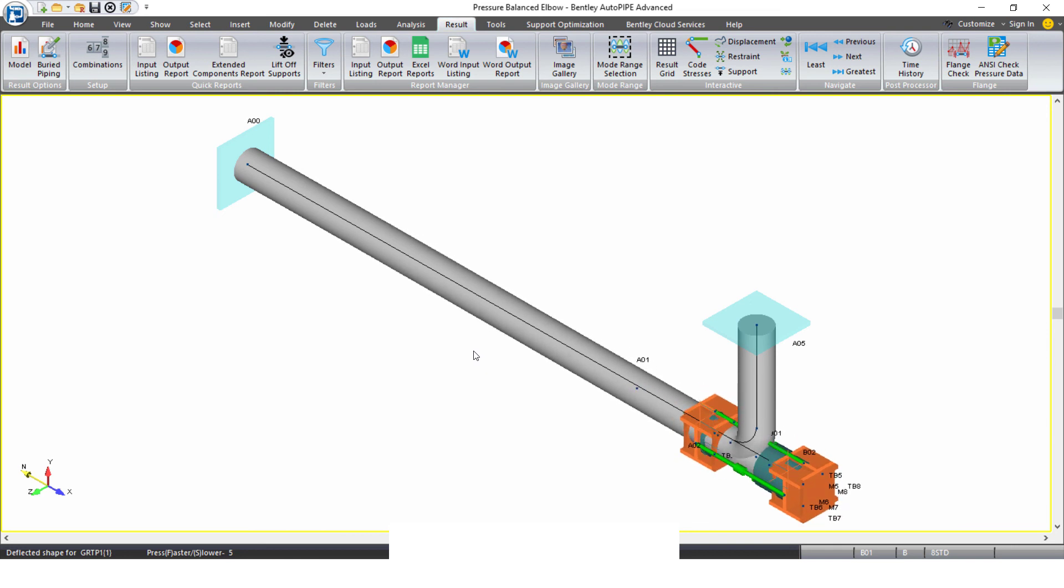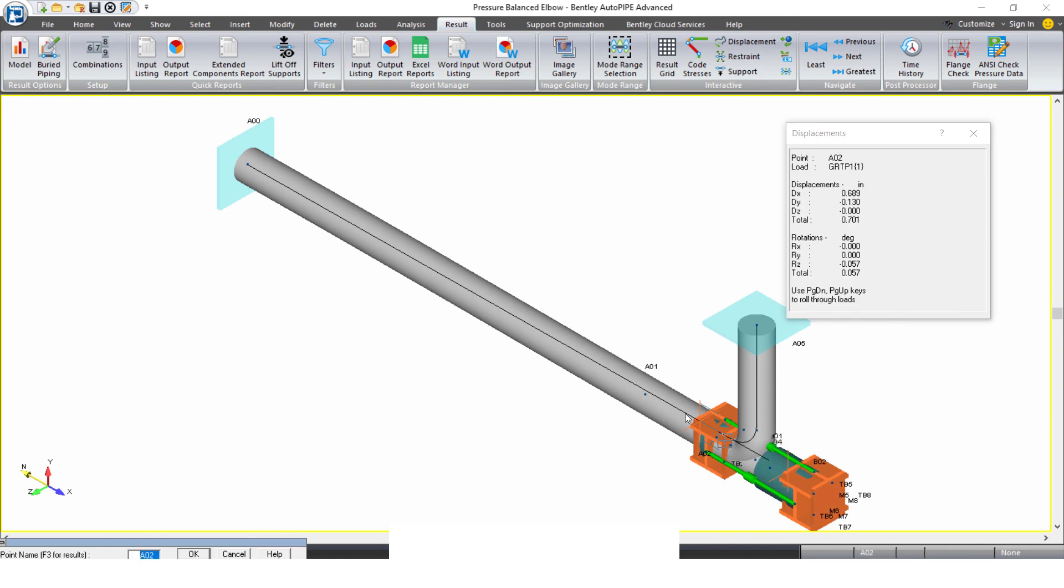We can see that there is no lateral movement, so the single bellows on the left is enough. It doesn't look like it's moving laterally. If I look at the actual values, it's not moving in the Z direction at all, so the single bellows on the left side is enough. I don't need that tied universal combination.